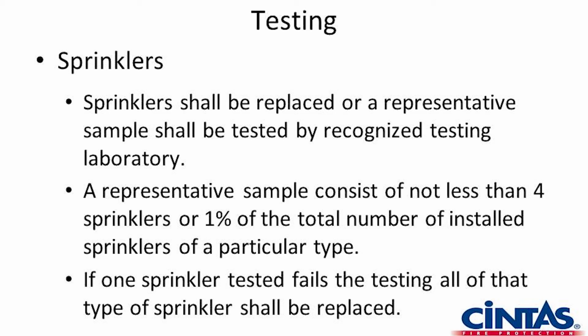When we remove those sprinklers, immediately we attach a tag that UL provides, and we write down the date. We write down the location that it was taken from. And for each different area, and I'm not speaking about East Wing or West Wing, I'm talking about condition: outside sprinklers, inside sprinklers, sprinklers that are in colder environments, warmer environments. We have to send a sample from each of those areas, minimum of 4 or 1%, whichever is greater. That would be for the 50-year-old head.